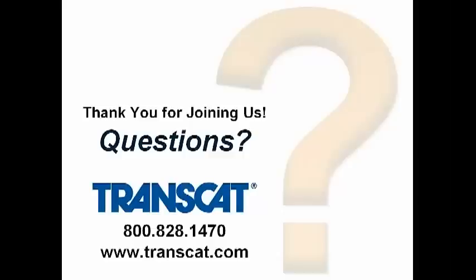Okay. To keep costs at an acceptable level, is there a generally accepted process to determine calibration cycles? NCSLI has a series of recommended practices. RP1 is all about adjustment of the calibration intervals, and there are 4 or 5, maybe 6 methods there, from very simple to very complex. There's also a company called Integrated Science Corporation that sells software to help you determine some of the more complex calibration interval adjustments. But RP1 is a good place to start, and take a look at that at ncsli.org.